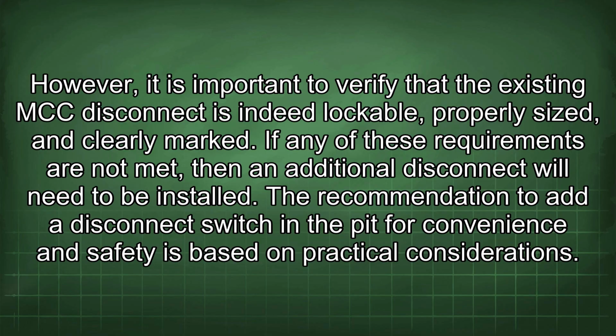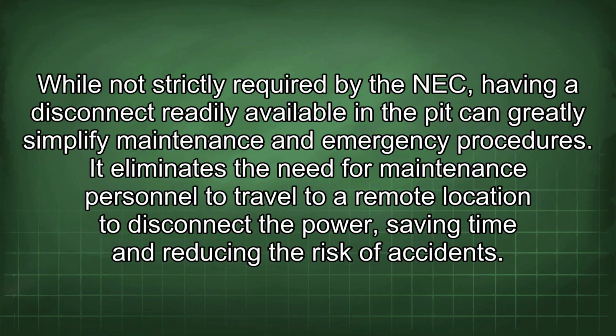The recommendation to add a disconnect switch in the pit for convenience and safety is based on practical considerations. While not strictly required by the NEC, having a disconnect readily available in the pit can greatly simplify maintenance and emergency procedures. It eliminates the need for maintenance personnel to travel to a remote location to disconnect the power, saving time and reducing the risk of accidents.